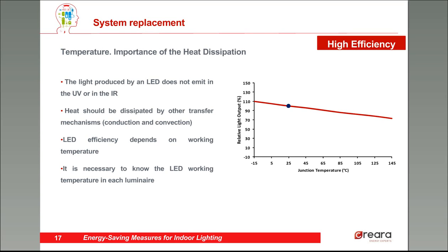Temperature is also an important factor in LED efficiency — maybe the most important factor. Remember, the light produced by an LED does not emit in the UV or in the IR, so the heat should be dissipated by other transfer mechanisms: conduction or convection. The graph on the right shows how efficiency decreases with the system temperature — as the temperature increases, LED performance and efficiency are lower. So we need a dissipator. One of the most important parts of LED luminaires is the heat dissipator, which helps the heat transfer so the temperature won't become too high.